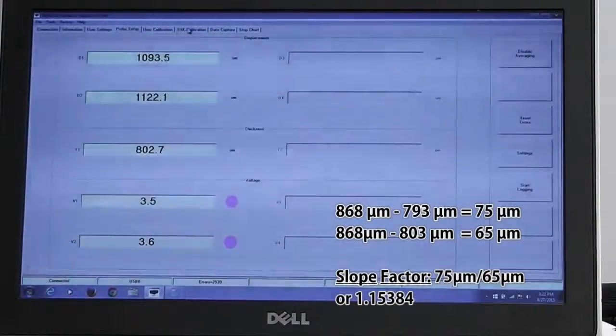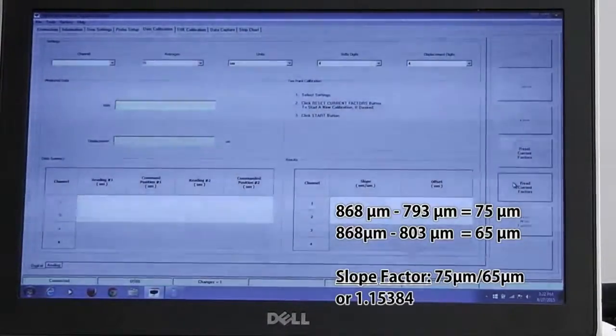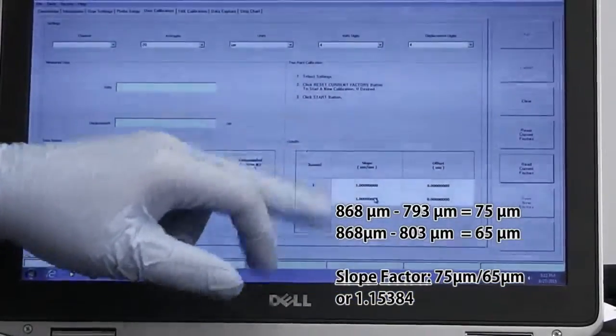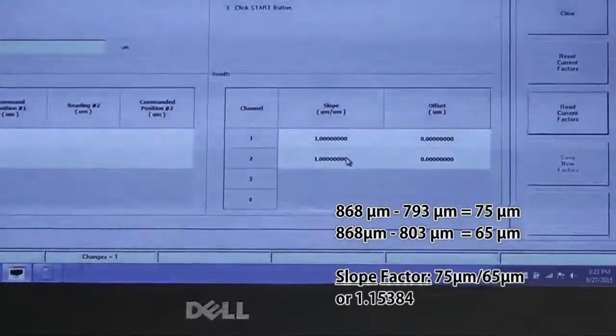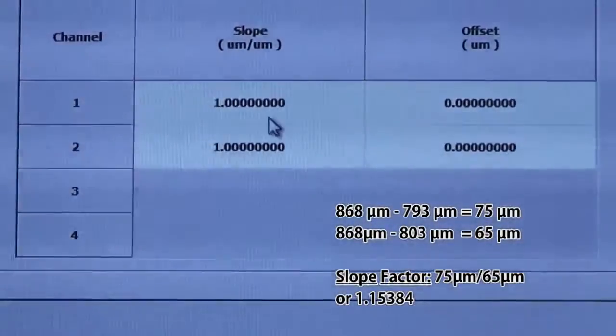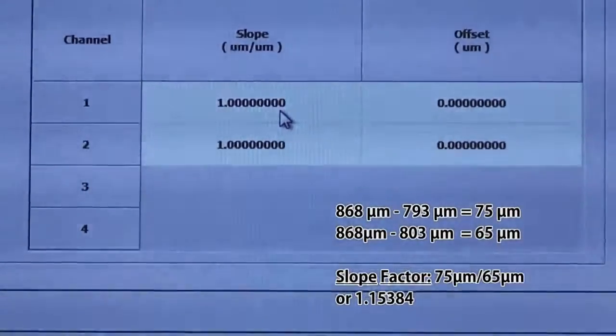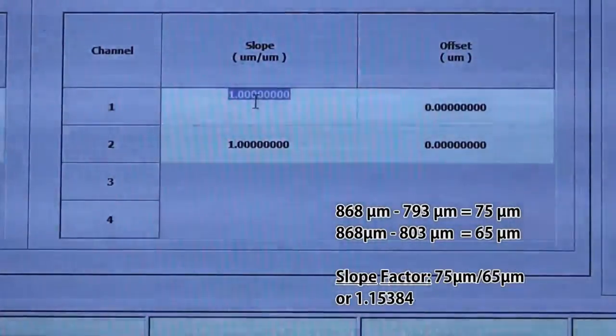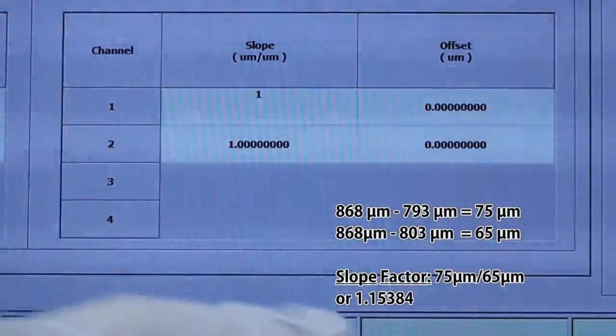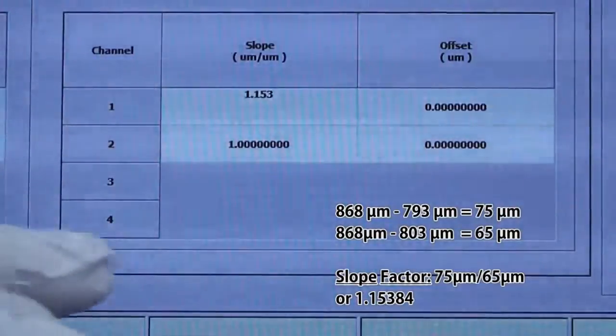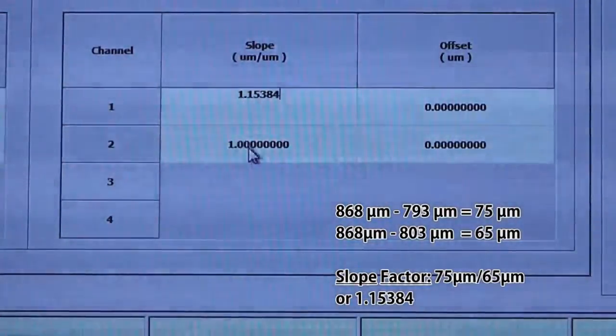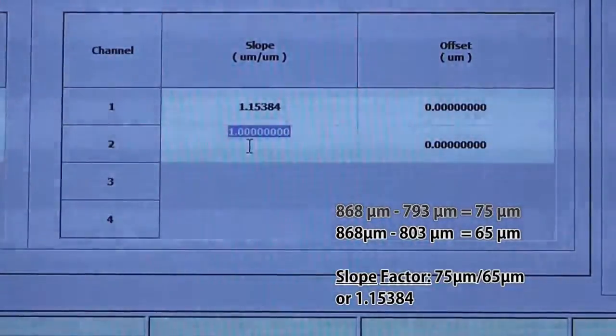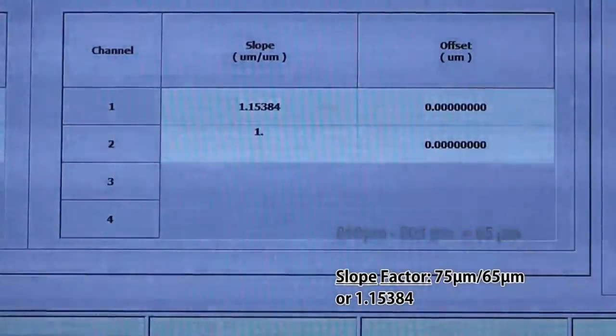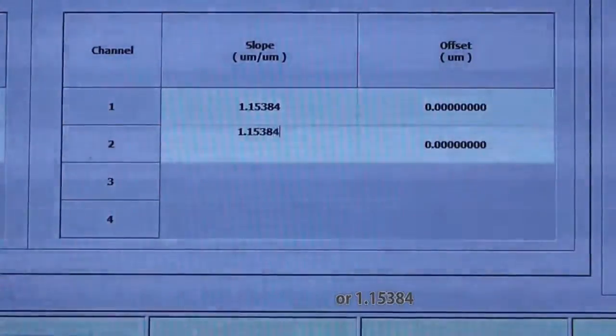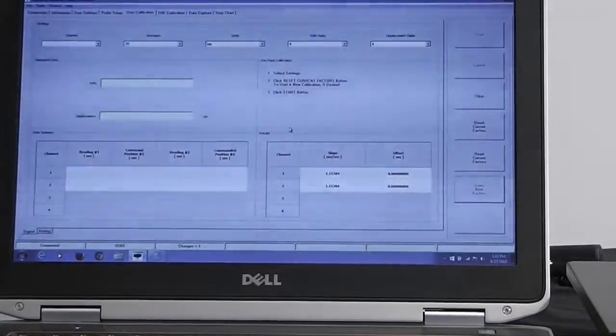So the next thing we're going to do is go to the user calibration window. We're going to read the current slope factor, which is 1 from our original calibration when the unit was calibrated in MTI. And our slope and offset is 1 and 0. What we're going to do is change these to the new slope factor. So I double click on this and I key in the sapphire slope factor, 1.15384. That's entered in channel 1 and channel 2 for both probes. Once those are keyed in, we click on the Save New Factors button. So our new slope factor is now saved to the system.